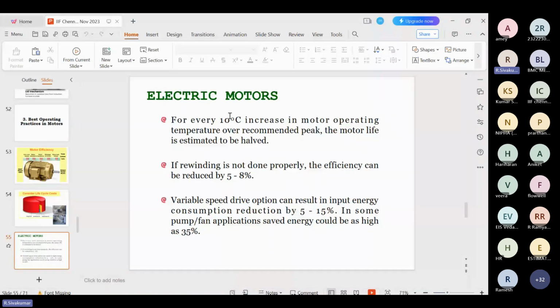Even the thermometer itself lets you see the hot spots on the equipment. So every 10 degrees, the life will be halved. So the temperature should be maintained at the optimum. And if rewinding is not done properly, the efficiency can be reduced by 5 to 8%. And a variable speed drive, VFD, can be adopted wherever possible. You can save almost 5 to 15%.